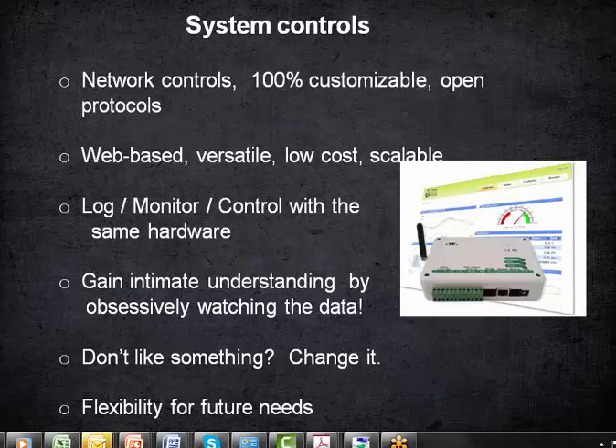So it comes off the shelf with the ability to go 40 in, 40 out? Right, but there's not 40 outputs or inputs on that main supervisor itself—in other words, the terminals aren't there on that one. There's only 2 outputs and 4 inputs.